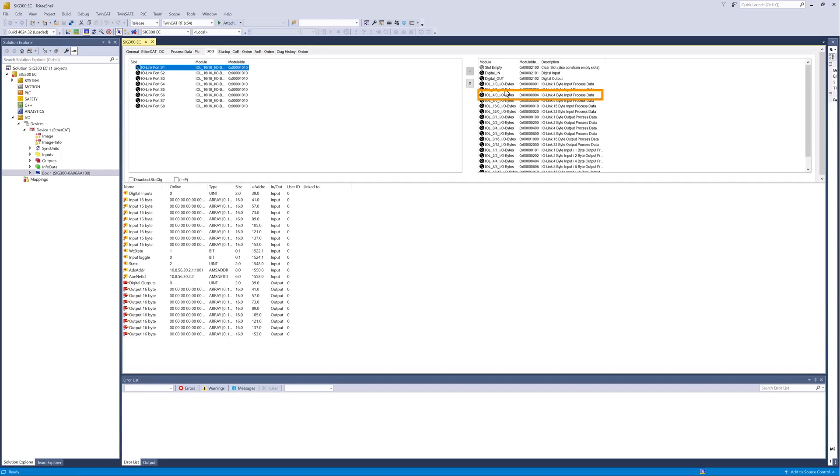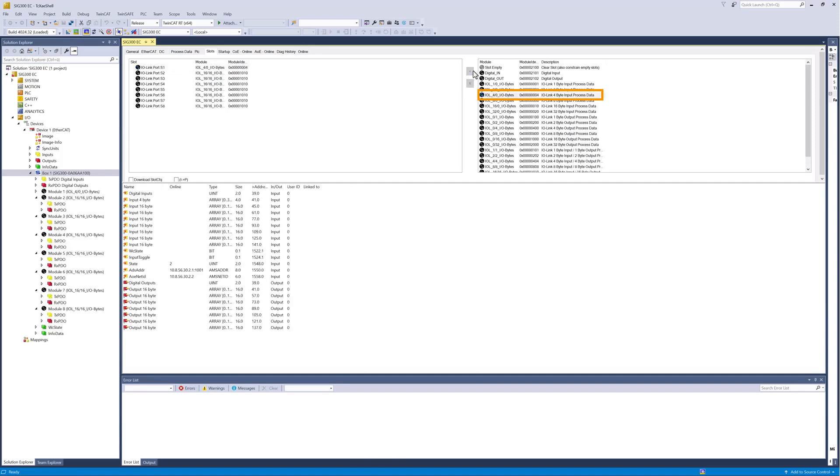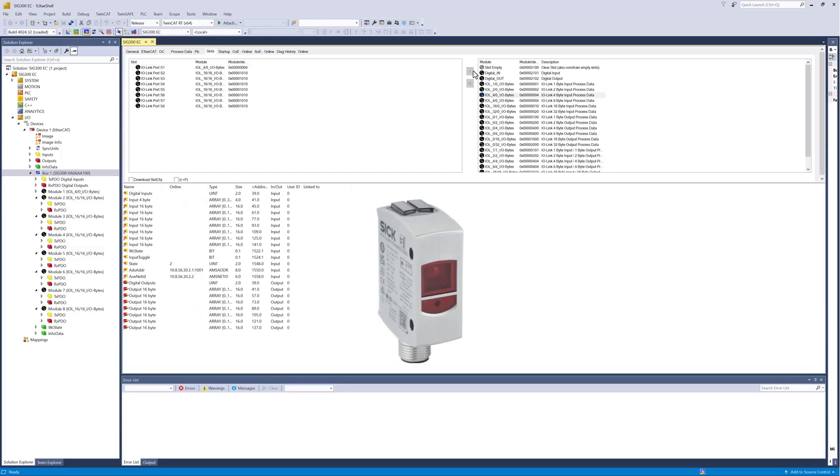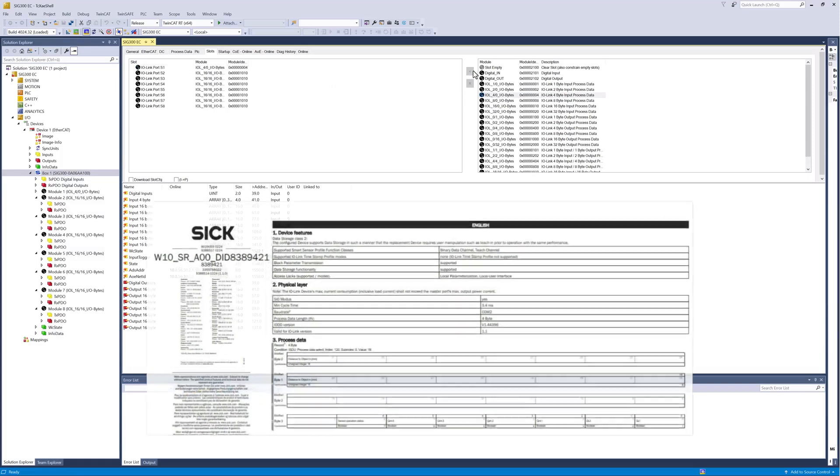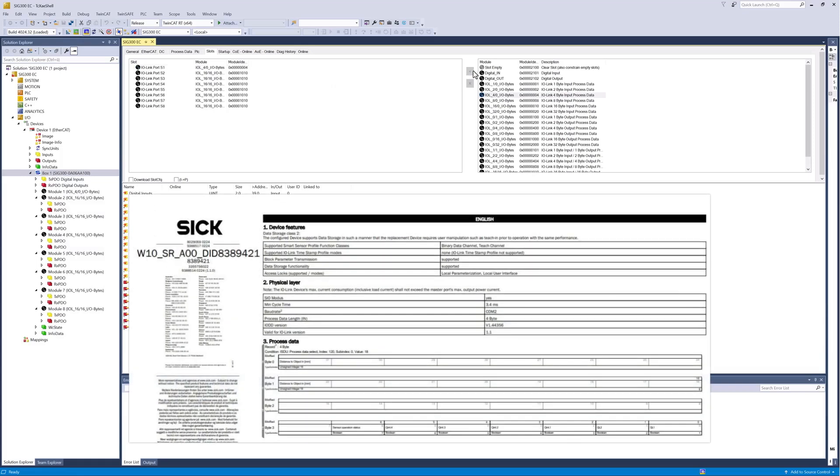When selecting an IO-Link module, please ensure that the process data of the connected device fits into the respective module. In this example, we connect a SICK W10 IO-Link photoelectric sensor to master port S1. As specified in the operating instructions, the sensor supplies 4 bytes of process data input. If no module with the correct amount of bytes of process data input is offered, we select the next larger module.